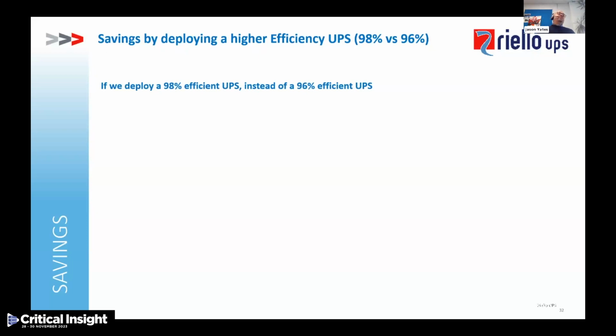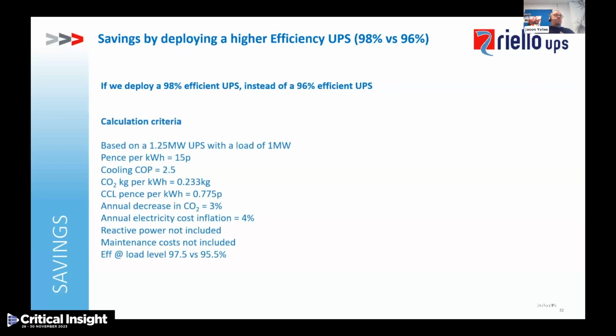if we deploy the 98% efficient UPS instead of a 96% efficient UPS, I want to be open about what we base this calculation on: a 1.25 megawatt UPS with a 1 megawatt load, and a cost of 15 pence per kilowatt hour. Obviously, it depends on the various sites and the customers. Cooling coefficient, we've put at 2.5. Obviously, this can change depending on sites. We've used CO2 per kilowatt hour of 0.233.